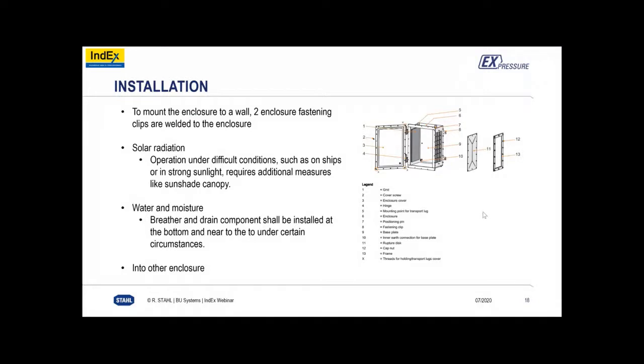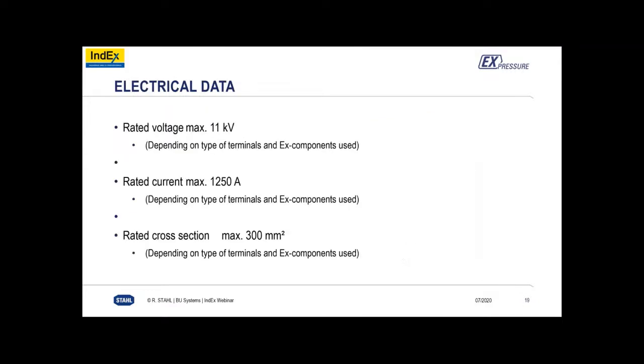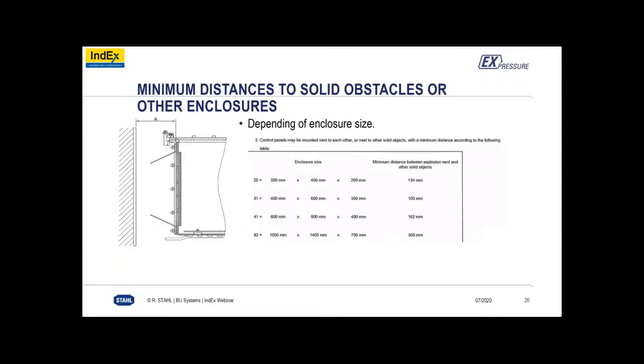So a typical EXD box, just with these 3 added components on each side: the mesh, the rupture disc, and that frame. That's the EXS main components, but it's also tested and certified. So the maximum rated voltage, obviously, as you mentioned, was 11 kV, depending on the terminals. Maximum rated current, 1250, and maximum cross-sectional area was 300 millimeters squared. So it's a big enclosure that can handle high voltage, obviously 11 kV, and a very high current. So it's a very flexible design.